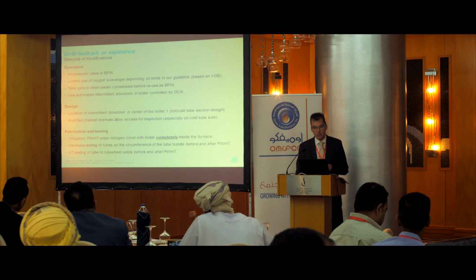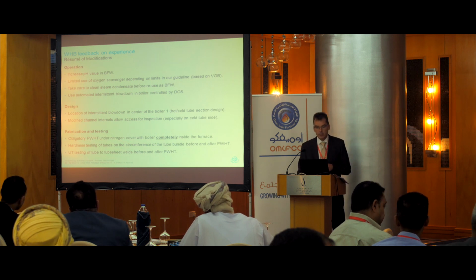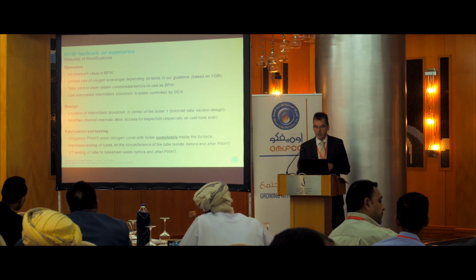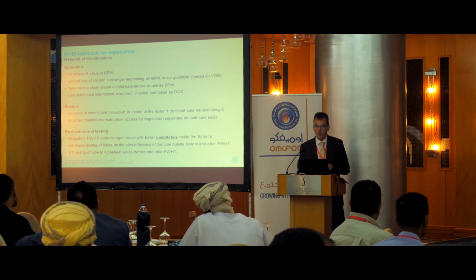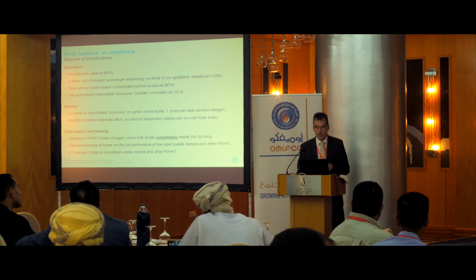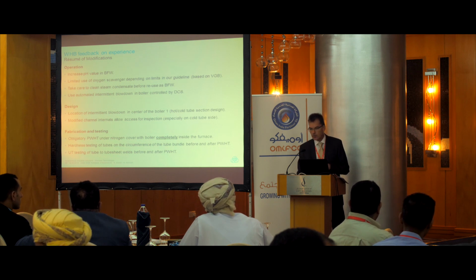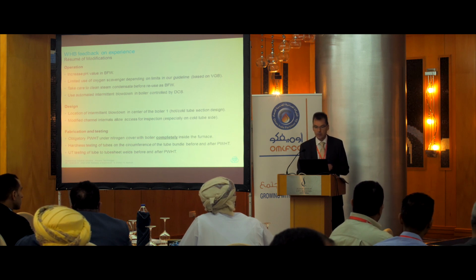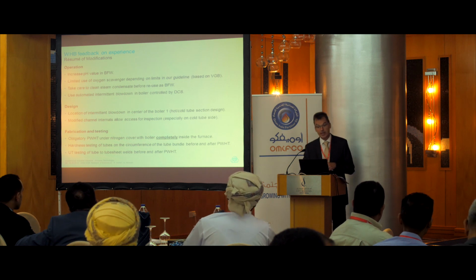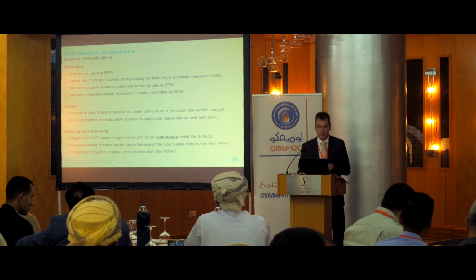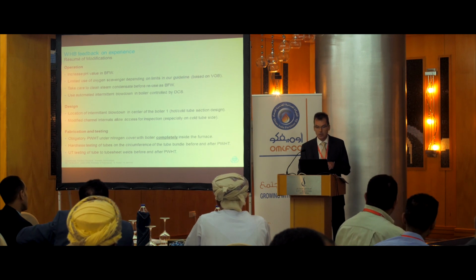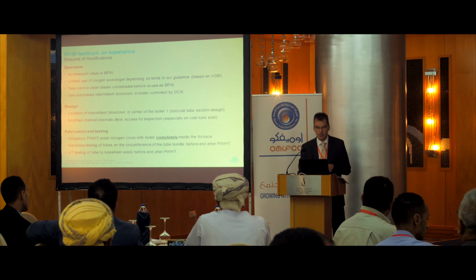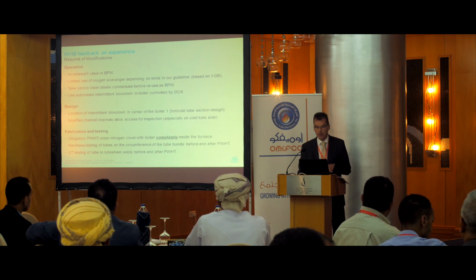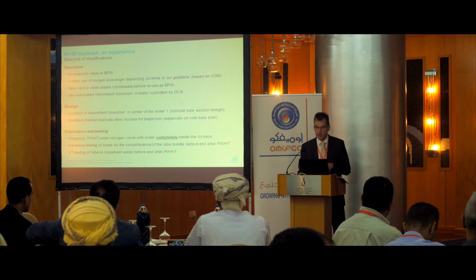What did we do with the design? You remember we changed the hot-cold sections of the tube sheet, so we now have an intermediate blowdown in the center of boiler number 1. And we have modified the channel internals so we can better check, during turnarounds, the status of the waste heat boiler with eddy current tests. What is important for fabrication testing? We said before: obligatory post-weld heat treatment under nitrogen cover with the boiler completely inside the furnace. Hardness tests on tubes are mandatory, and ultrasonic tests of tube-to-tube sheet welds before the post-weld heat treatment are also mandatory.